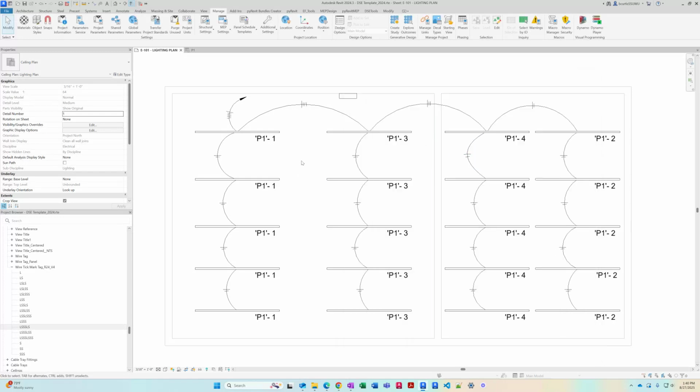And you can see that we have the same problem we had before. This wire is fine. Circuit 2 is shown as it should be, a long and a short. This one is actually still shown correctly because these two share a phase, so we've got a long, short. But when we get to this one, we're back to the same problem. So we should have a long, short, long, short, because 2 and 4 will share a neutral, and 3 will have its own neutral, and then this one is wrong as well for the same reason.